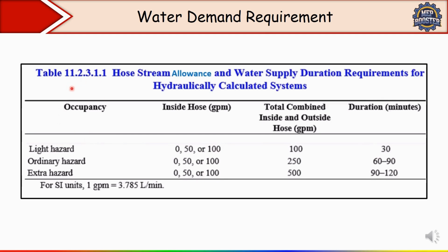Okay, so first, if you see the table, if a building has partial automatic sprinkler, the parameter is not fully sprinkler protected. The parameter is the occupancy, only in any one of the floors you have. So this refers to the hazard. So the flow rate required by this light hazard section, which is given here, 7.10.1. Already the standpipe demand must be increased by what is actually, which building comes under light hazard, which building comes under ordinary hazard: 150 GPM. Already we have discussed this for light hazard occupancy. Next thing, 500 GPM for ordinary hazard occupancy. Whichever is less, the rate in GPM should be considered in the calculation.